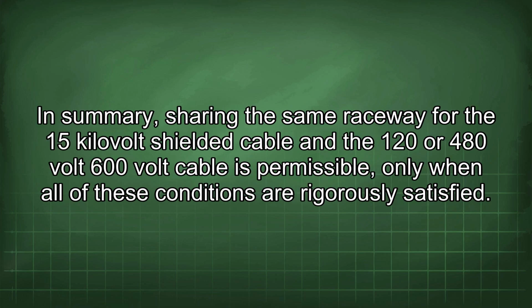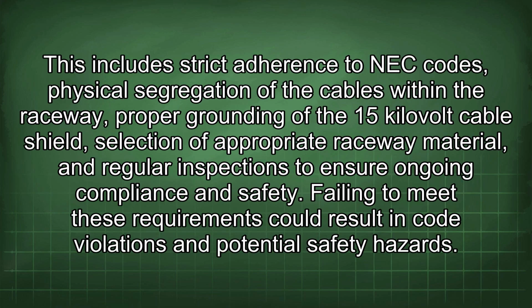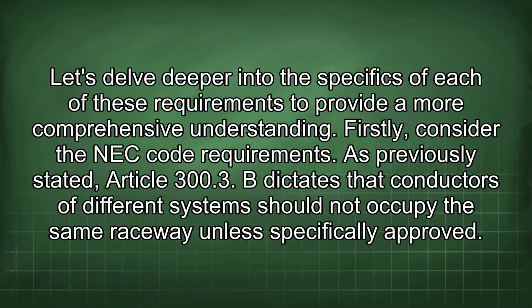In summary, sharing the same raceway for the 15 kV shielded cable and the 120 or 480 V 600 V cable is permissible only when all of these conditions are rigorously satisfied. This includes strict adherence to NEC codes, physical segregation of the cables within the raceway, proper grounding of the 15 kV cable shield, selection of appropriate raceway material, and regular inspections to ensure ongoing compliance and safety. Failing to meet these requirements could result in code violations and potential safety hazards. Let's delve deeper into the specifics of each of these requirements to provide a more comprehensive understanding.